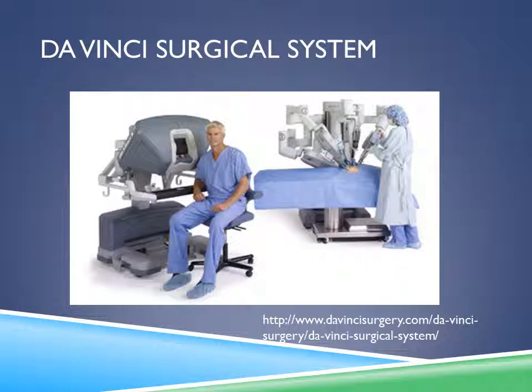And with the Da Vinci system, the way it works is that small incisions are used to introduce mini wristed instruments and an HD 3D camera. And seated comfortably at the Da Vinci console, the surgeon views a magnified HD or high resolution 3D image of the surgical site, and at the same time, the robotic and computer technology scale, filter, and seamlessly translate the surgeon's hand movements into precise micro movements of the Da Vinci instruments. The system can't be programmed, and it cannot make decisions on its own. So basically the way it works is that every surgical maneuver is performed with the direct input of the surgeon.